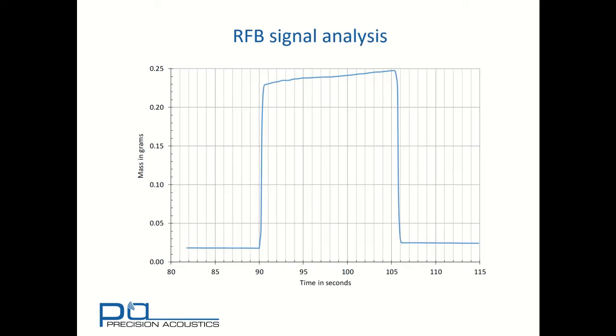So let's consider one of those traces in detail. The first thing to note is the change in baseline on either side of the peak. Here, a dotted line has been introduced to show this variation. We can also see, as shown by the oval, a little oscillation immediately following the ongoing transition. This is common with transducers that take a while to achieve a steady state.